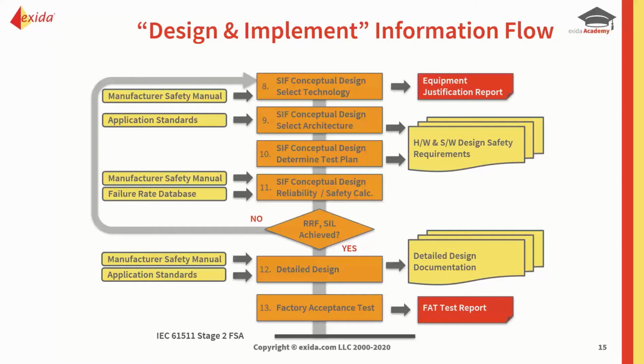Then we get into detailed design once we've done that for all the SIFs. And this is where we need to develop our application program. There are tools, and Excellencia is one, that will create cause and effect automatically from the SIF design. And then you can take that cause and effect, and then you create your application for each of the SIFs. Based upon that, that's one approach. So we have to be, again, very methodical in how we do that.